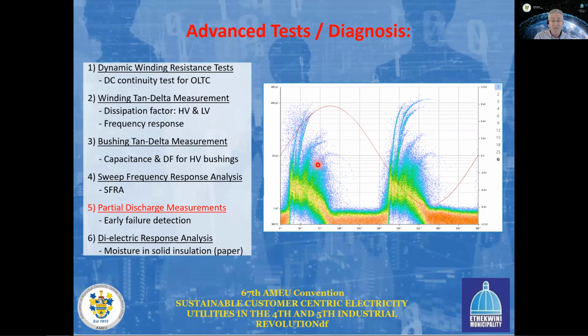For this kind of test, it's very important also to be able to separate the actual discharges that are happening as a result of the partial discharges from any noise that is measured around the transformer and around the environment where we're testing. And in this case, it's very important to have noise filtering and partial discharge separation methods available when you're doing this kind of test.